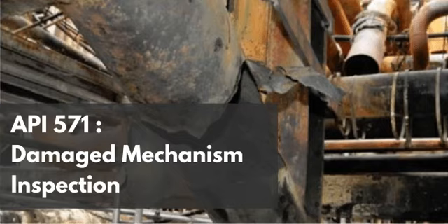Wow. So even before you put this tube into service, before it ever sees a single drop of fluid or a single PSI of pressure, it's basically sitting there internally screaming with residual tensile stress. Precisely. Just from the manufacturing process alone. You have a highly susceptible copper-zinc alloy, and you have maximized its internal stress through cold work.